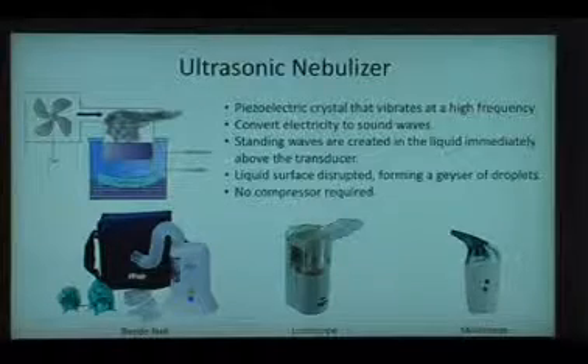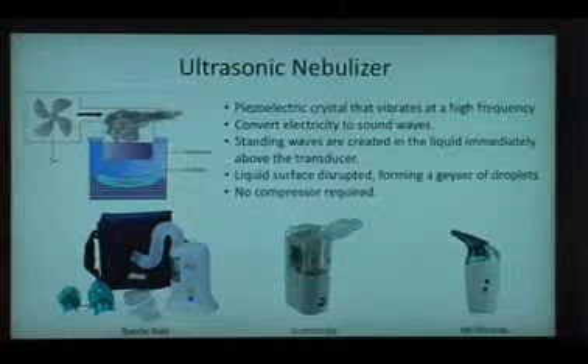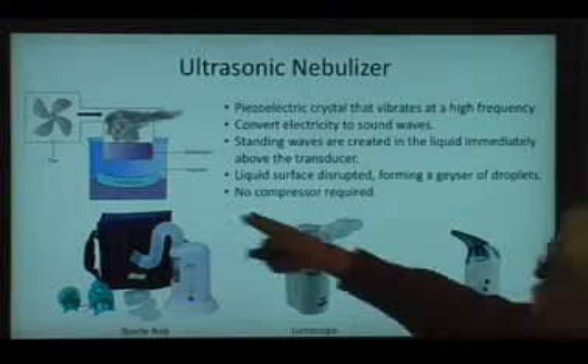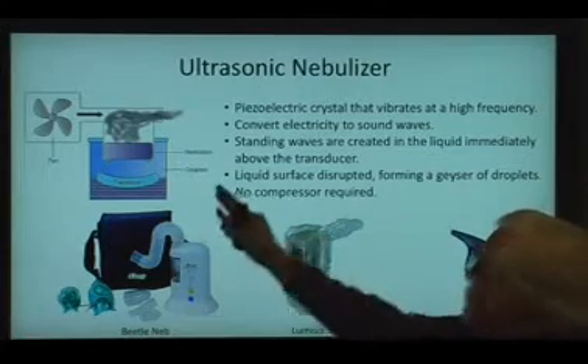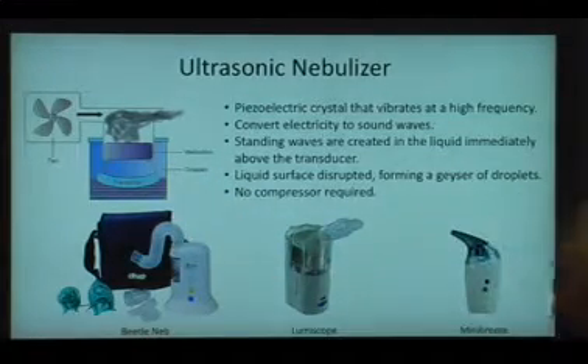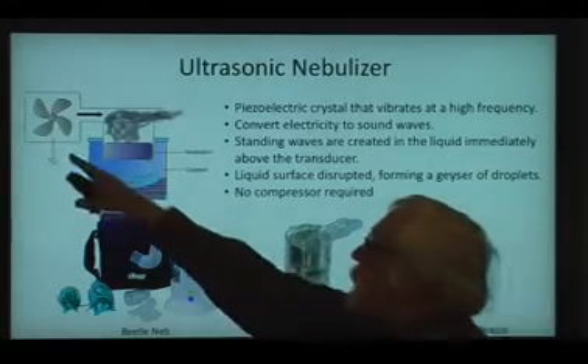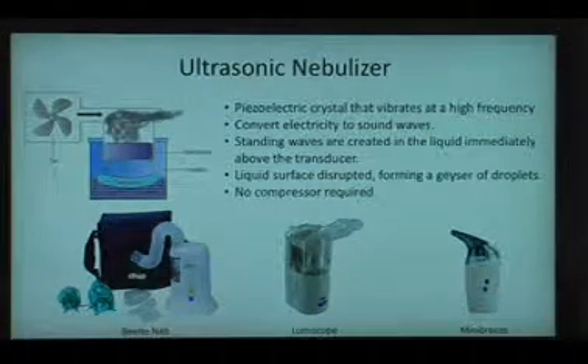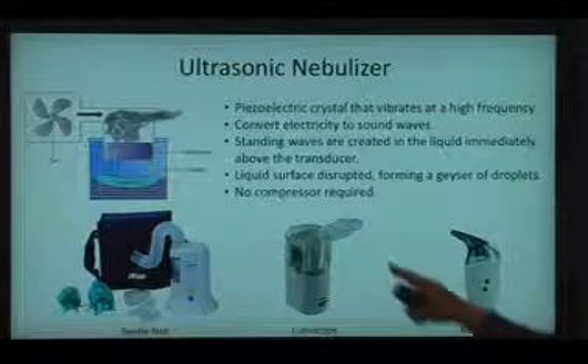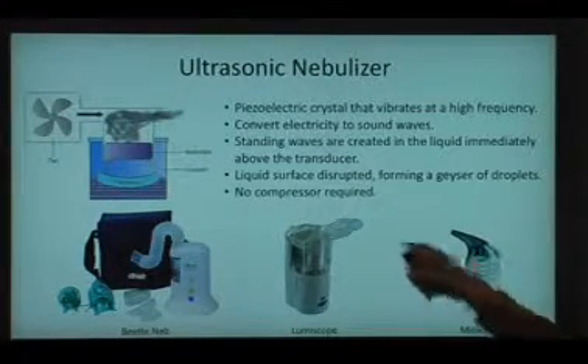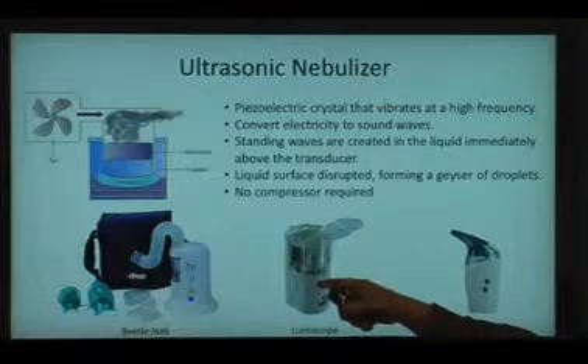So what about the ultrasonic nebulizer? This uses a piezoelectric crystal, in this case the transducer, that vibrates at a high frequency. That converts electrical energy applied to the transducer to sound energy. That sound is concentrated on the surface of the liquid, and that produces the aerosol. Then there can either be a fan to blow the aerosol to the patient, or, for handheld devices the patient might use at home, the patient just breathes through the medication cup to get the aerosol. These handheld devices intended for home use are actually ultrasonic nebulizers.